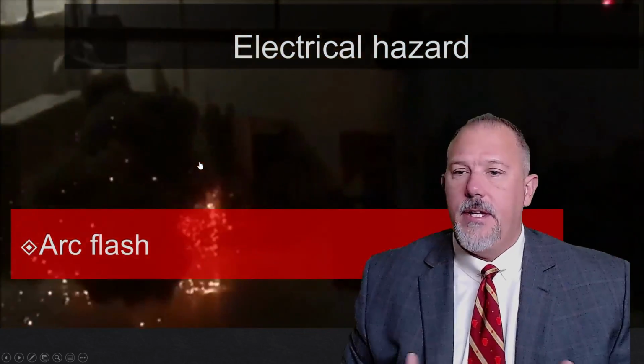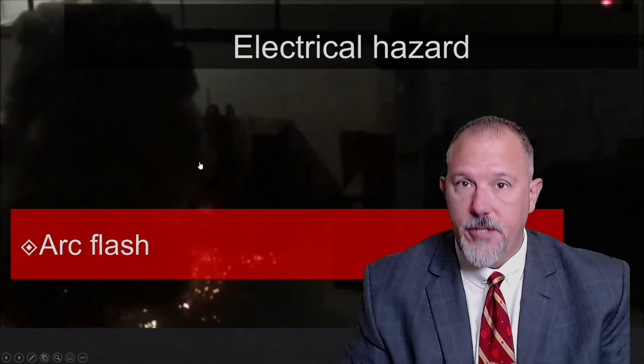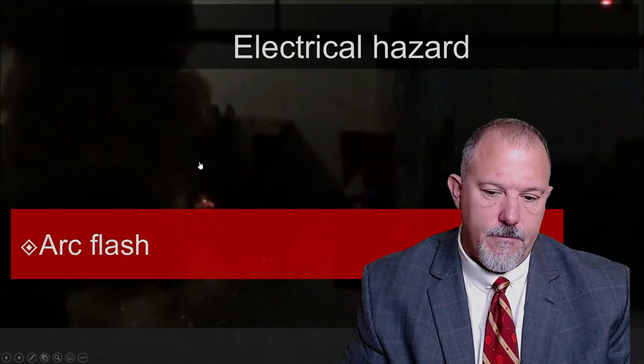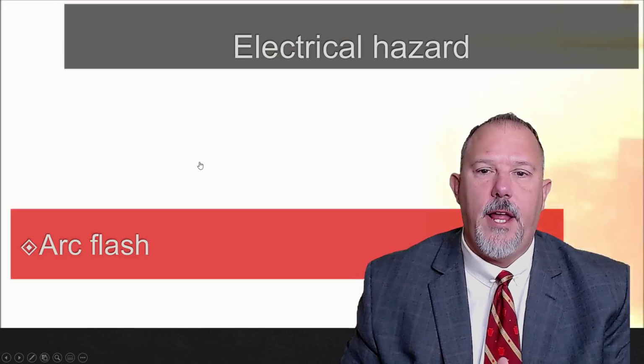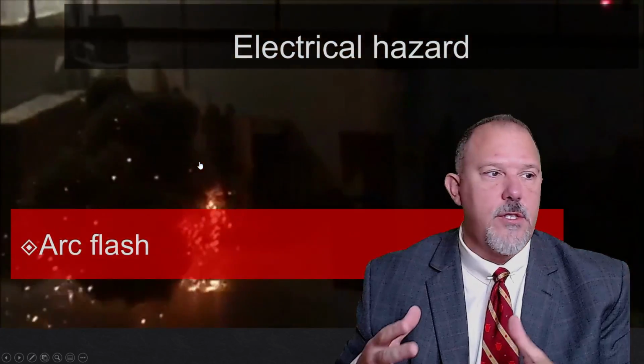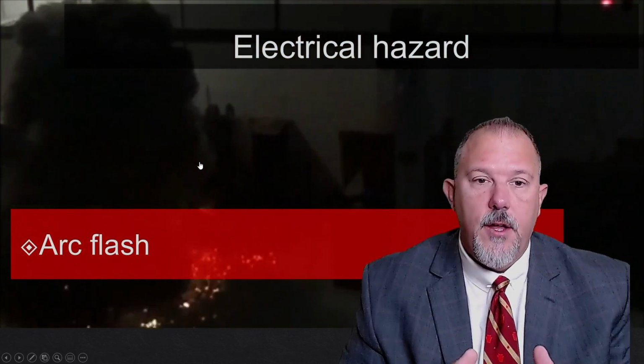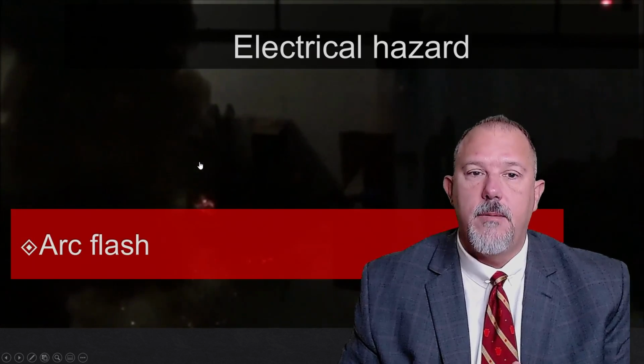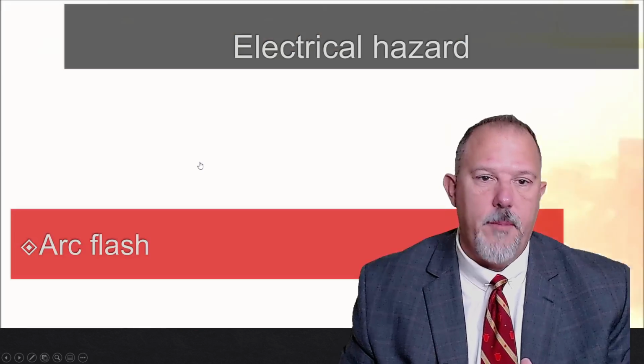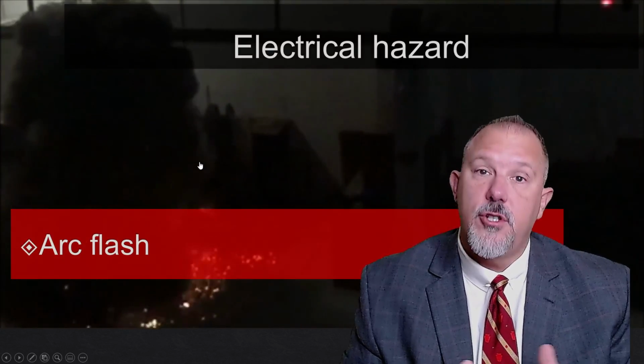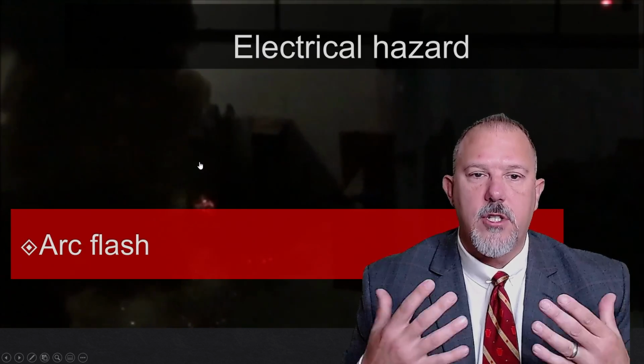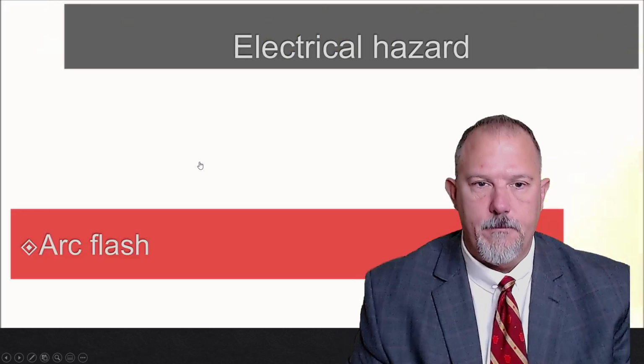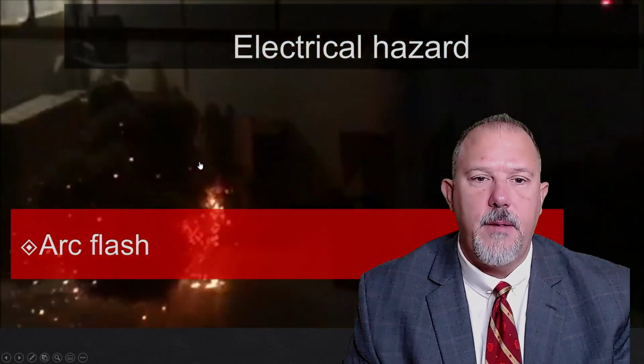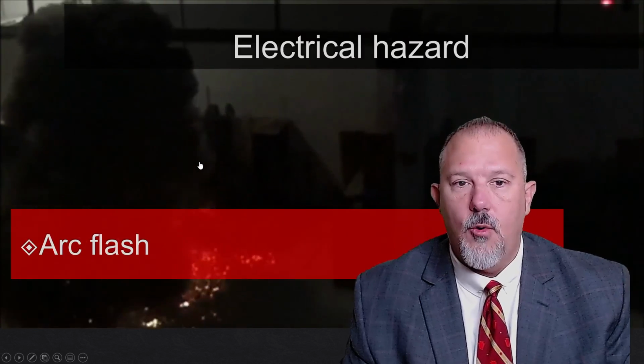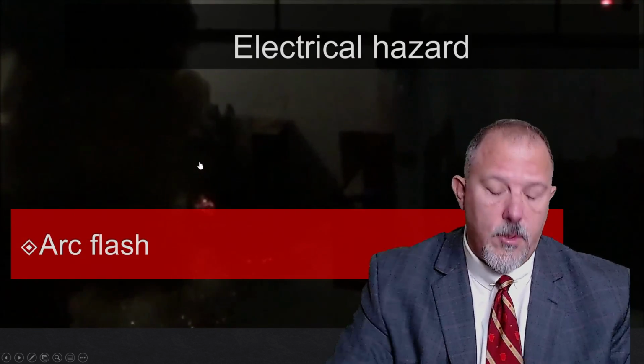Now, an arc flash event is a rapid release of energy. I've looked through many references, and there's not a standard that actually defines the term arc flash, but we know it when we see it. What I'm showing here is a slow motion video of an arc flash, and this is in a lab environment. There's nobody there in front of that equipment, but this is a simulated arc flash event that has been created in a laboratory to demonstrate the power. And you'll see what looks like a vibration in the video, and that's not the camera moving. That oscillation is actually the bulletproof window that I'm standing behind when that event occurs, and that shows you the pressure wave that occurs during an arc flash event.